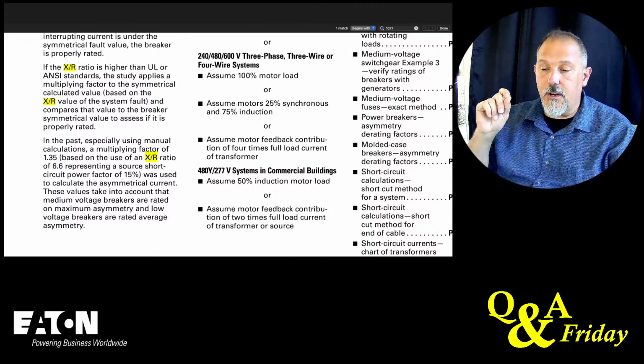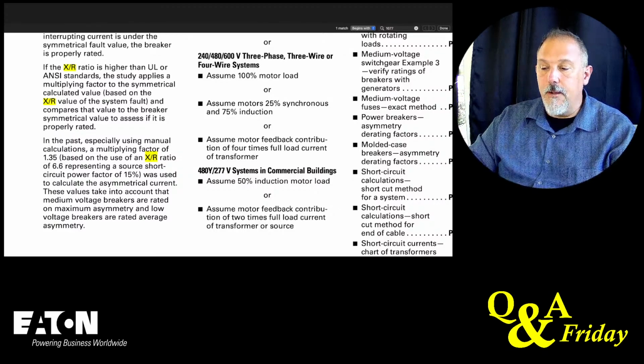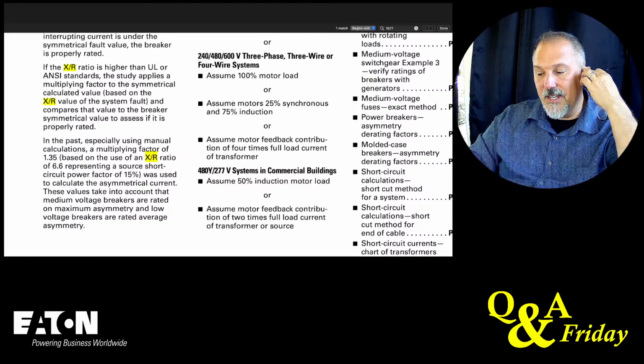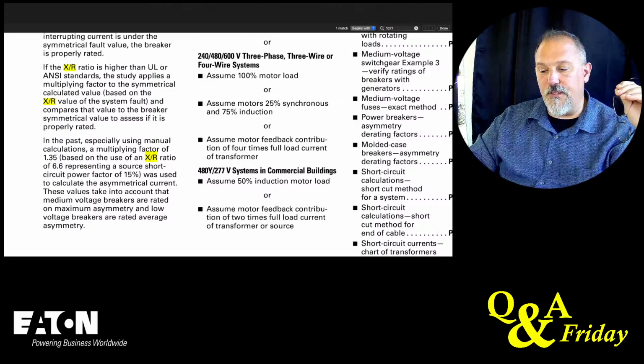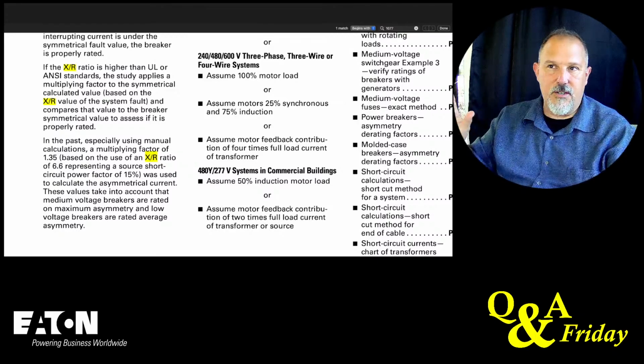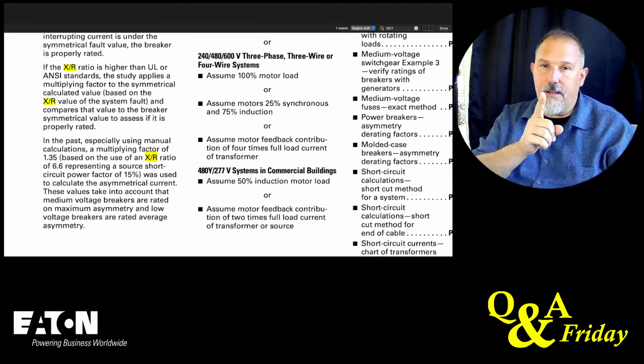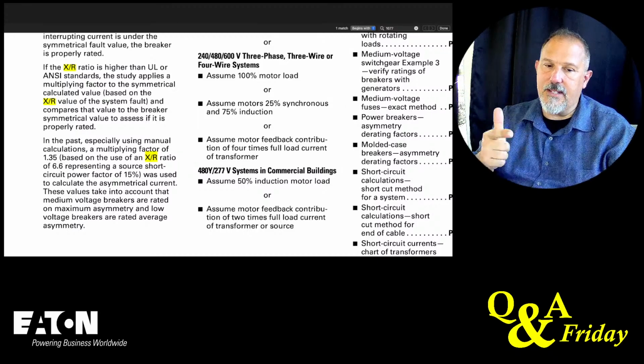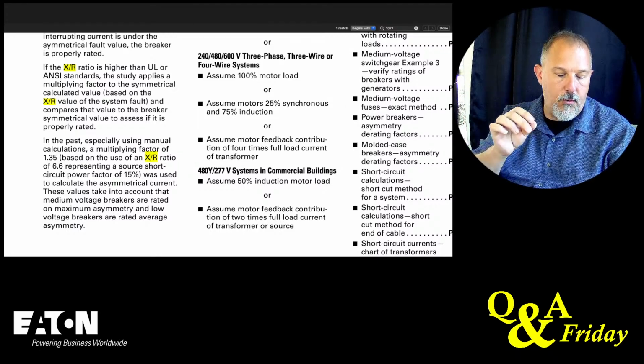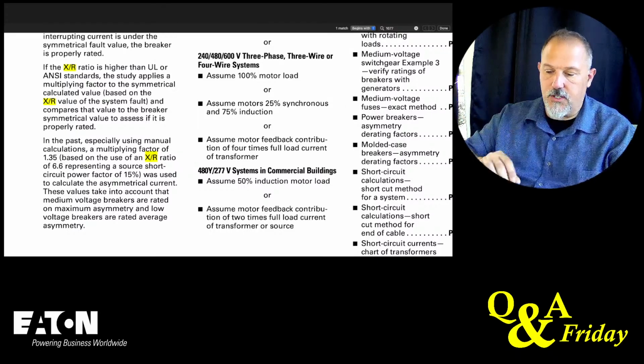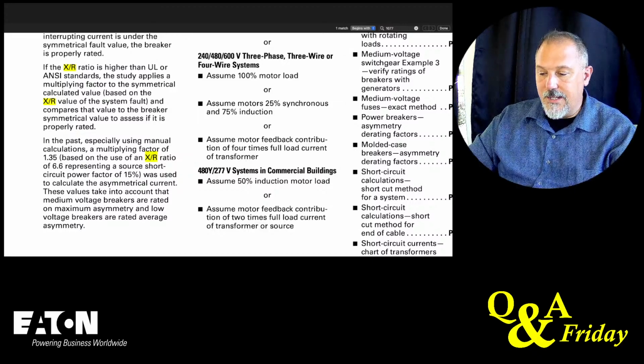Look at this. If the X to R ratio is higher than the UL or ANSI standards, the study applies a multiplying factor to the symmetrical calculated value. And remember, I said it was 1.6. This one here uses 1.35, and it all depends. And these are rules of thumb. But programs like SKM, EDSA, Easy Power, they'll all give you the value of X to R ratio. Now look at this.